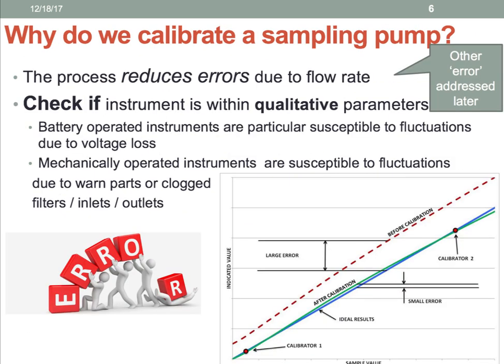So we calibrate our sampling pump to reduce errors and check if the instrument is within our qualitative parameters. We must remember that battery-operated instruments are particularly susceptible to fluctuations due to voltage loss, and our sampling pumps do try to adjust for any fluctuations within a certain range. Also, mechanical operating instruments such as our sampling pumps can have parts that become worn out — filters, inlets, or outlets which become clogged over time.